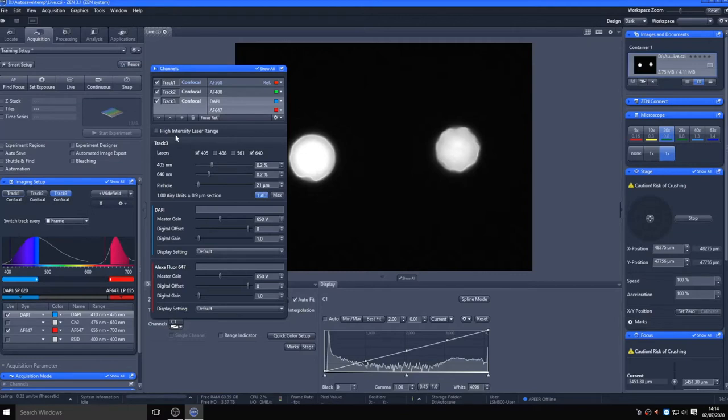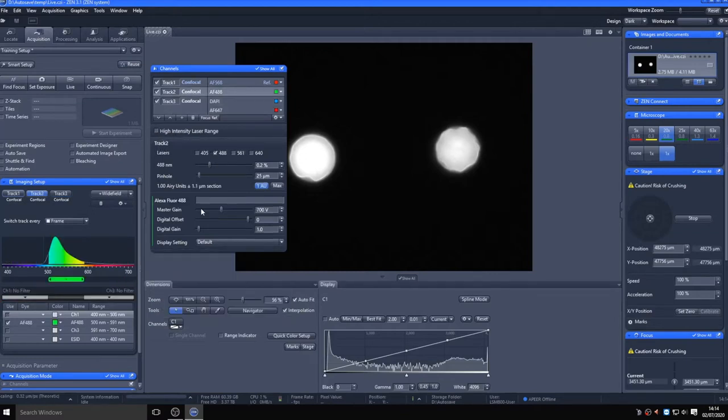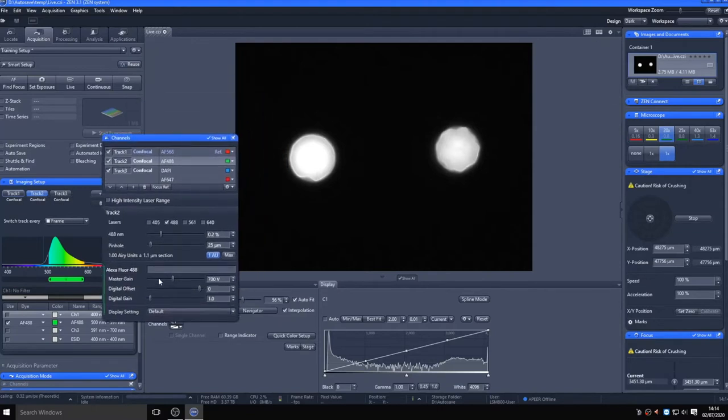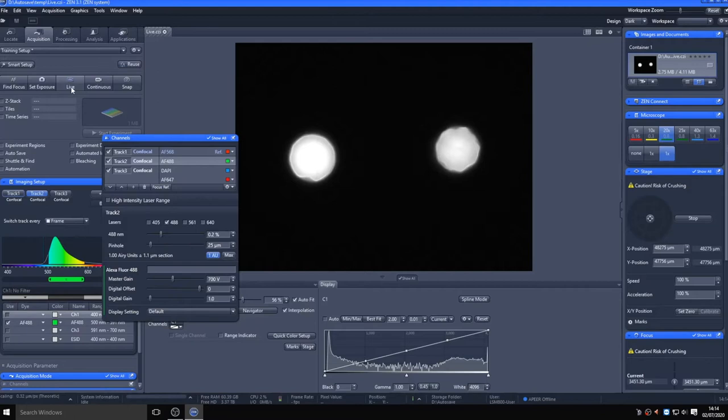Therefore, it is useful to be able to tailor the emission parameters as accurately as possible, so using the central detector instead for Alexa 488 will allow us to alter the wavelength from both sides. It is usually good practice to not have your collection wavelengths overlap the excitation line wavelengths to reduce the chances of picking up reflections, but the laser blocking filters in the LSM 800 are extremely effective, apart from the one on the 647 laser, which is designed to allow some reflection to be detected.